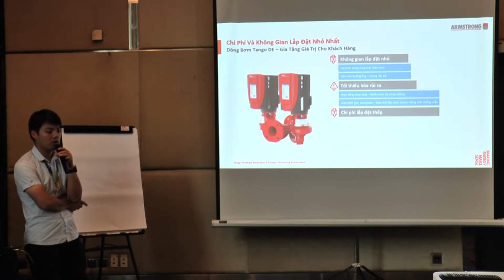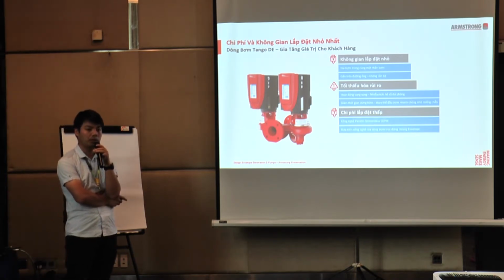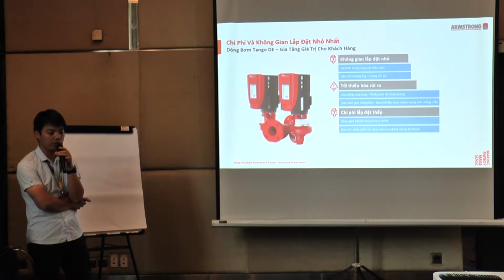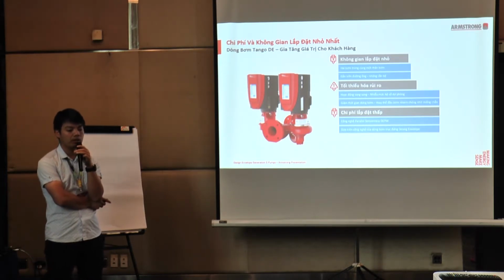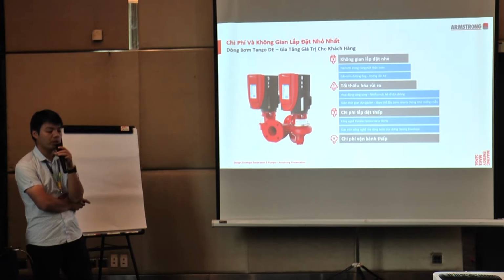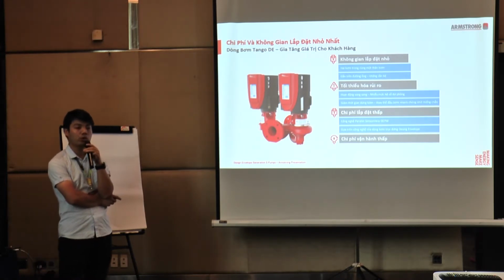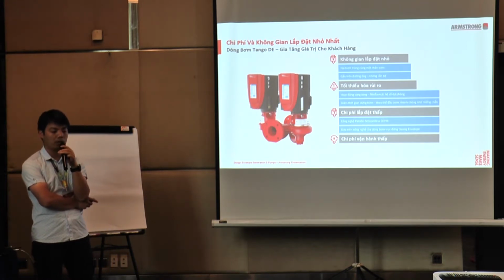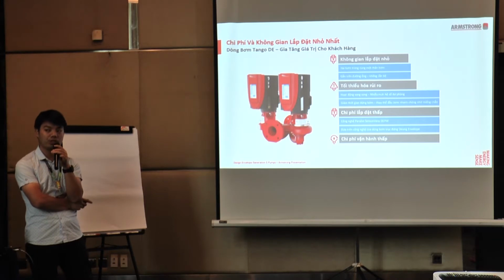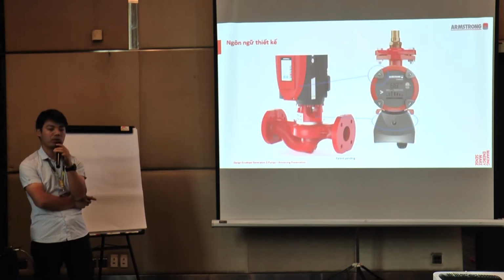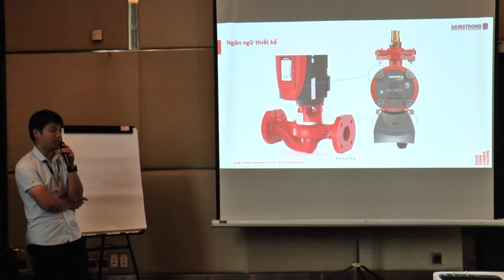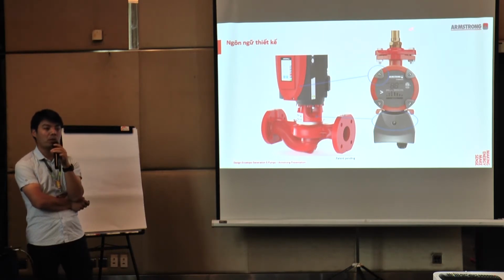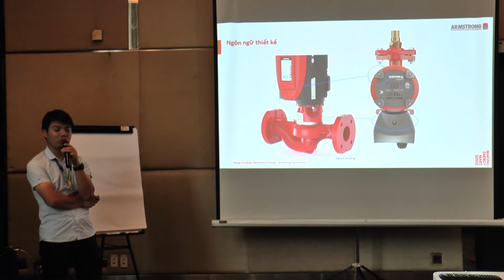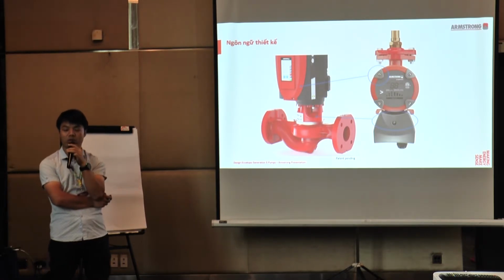And the lowest installation cost, and we can use our permanent magnetic motors with our parallel sensorless technology. And also the lowest operation cost. We have optimized our control integrations with our Gen 5 pumps, and also the most efficient stage sequences are embedded in our inverters. Now this is the newest appearance of our Generation 5 pumps. We can see all of the details have parabolic forms, and this reflects our quadratic curve controls.